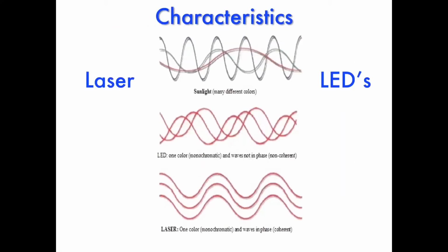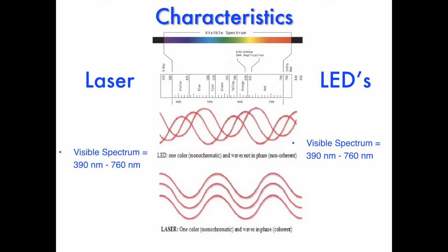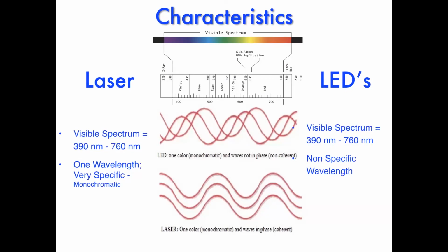So as we look at the characteristics of light therapy, you have sunlight, which is all spectrums. LEDs, even if it comes to a single dot, the waves are not parallel to each other and they're not monochromatic. It loses a lot of efficiency from a photobiological standpoint. So when you're dealing with true lasers, it's monochromatic, where 635 nanometers is 635 nanometers. Very little to no tolerance with that. 660 would be 660 nanometers. Okay, LEDs would scatter all over the place. They would not be monochromatic. They're not specific wavelengths, even though if on the paper it says that. If you put them on a photon meter, they would not be.